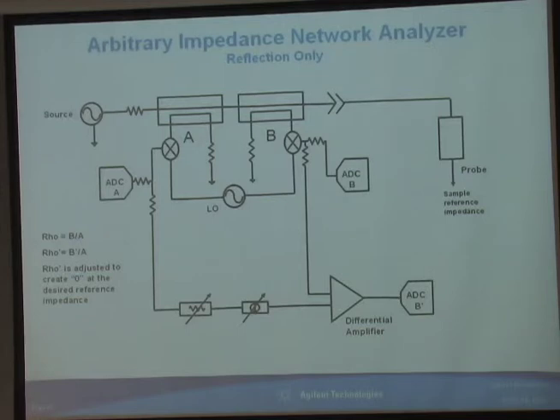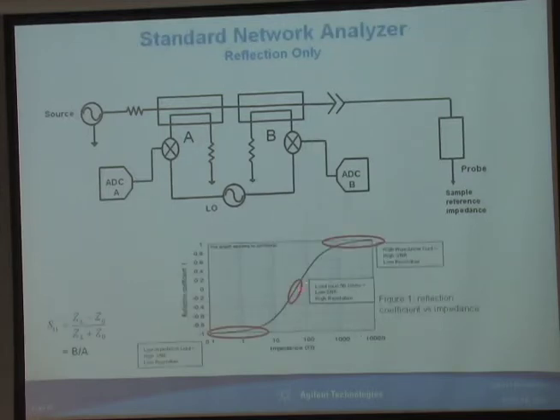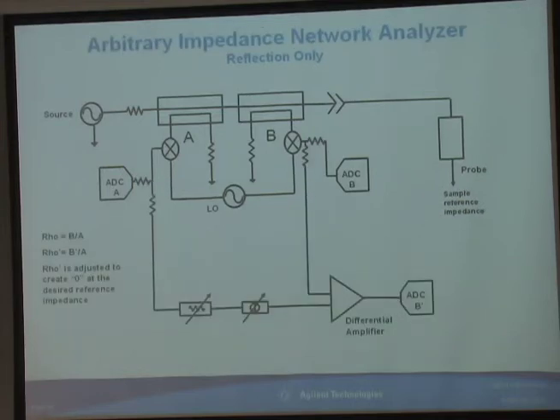So what that does is put you back here, but now this reads 50,000 for a reflection measurement. Now you're in the high slope region of the network analyzer. You're able to see 1 ohm differences around 50,000 ohms, which is something you want to do and can't do without this trick. Problem with this trick is it only works at one frequency, so you have to readjust it every time you make a different frequency measurement. It's also very sensitive, so it's hard to make a metrology-grade instrument out of this.